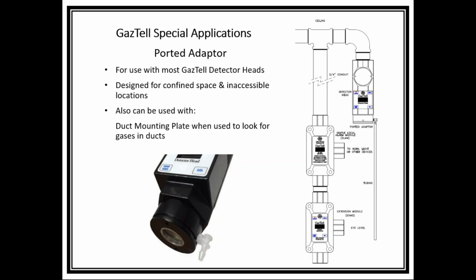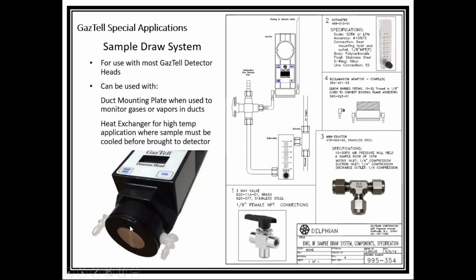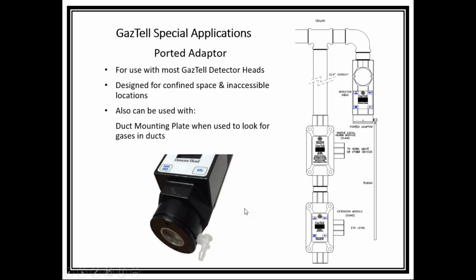Ported adapters are a really important feature on the GazTell. And the reason is, as I mentioned earlier, when using an XMO, let's say you have to place a sensor maybe above a dropped ceiling. Well, you're not going to be able to get to that sensor very easily to calibrate and obviously see the display. So you'd put it above the ceiling, use an XMO, bring it down to floor level, and using the port, which is just a port that allows a connection of a 1/8 inside diameter tube being brought down to ground level. And at ground level, you could use the XMO to mimic the functions on the detector head itself and do all the calibrations and actually port your gas up to the sensor.